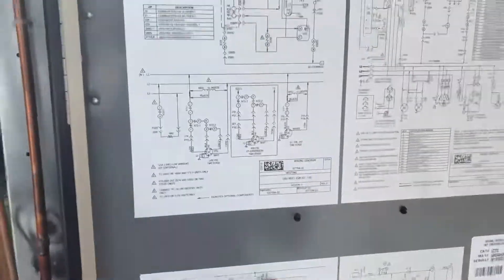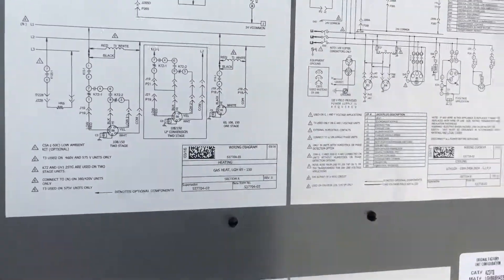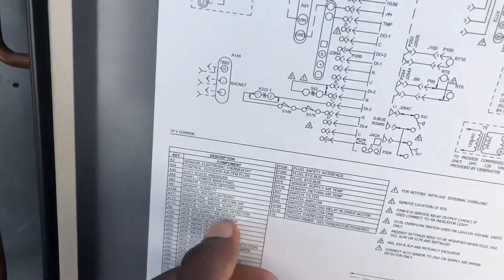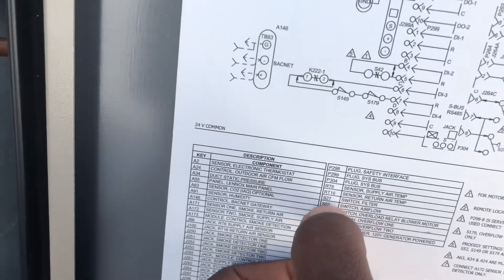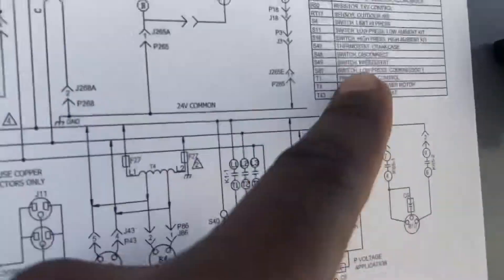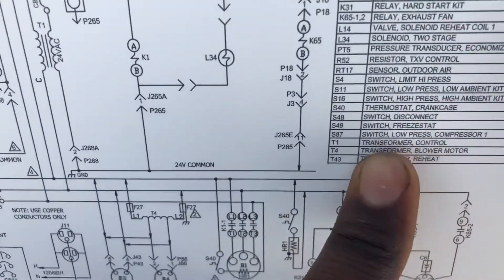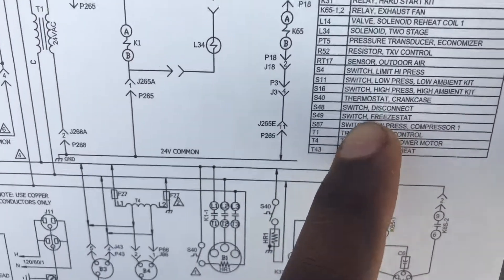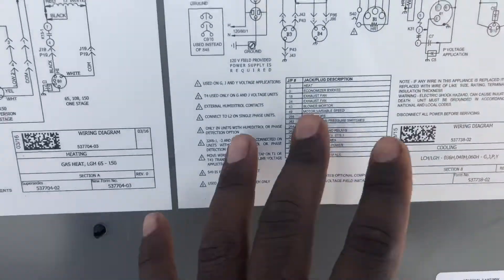If you look here on the door panel of these Lennox units, you always have your legend. So if it says S49, you look for your S49, which is your freeze stat switch. If that didn't tell you it was a freeze stat, you always have it here. Let me zoom in so you can really see — S49 freeze stat, freeze stat switch.